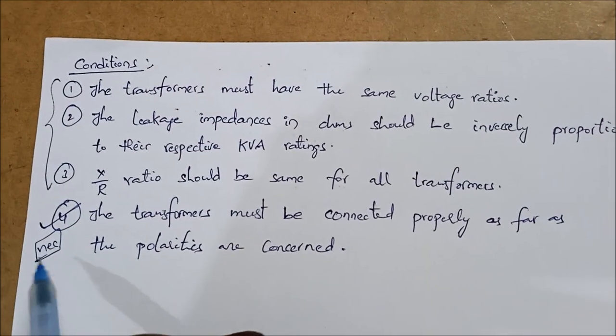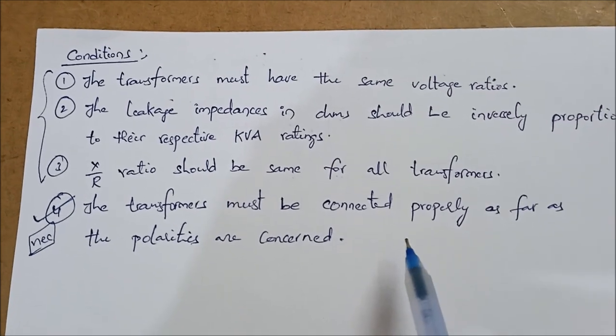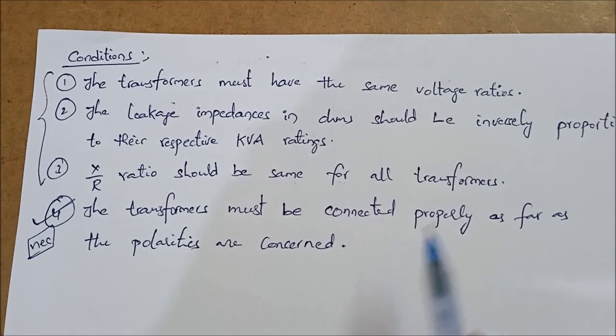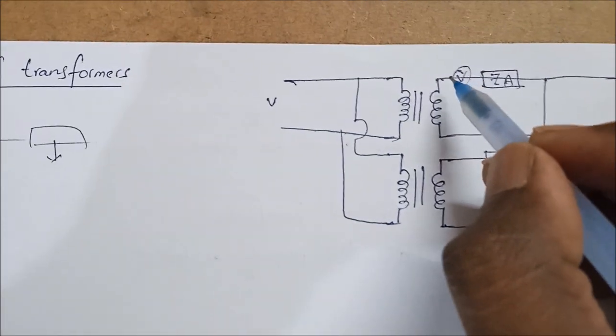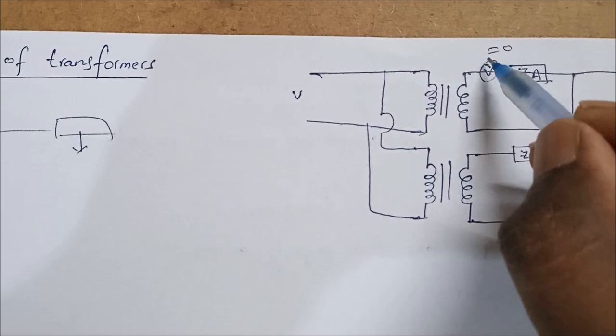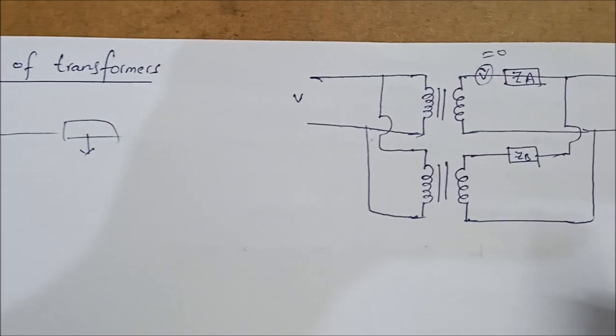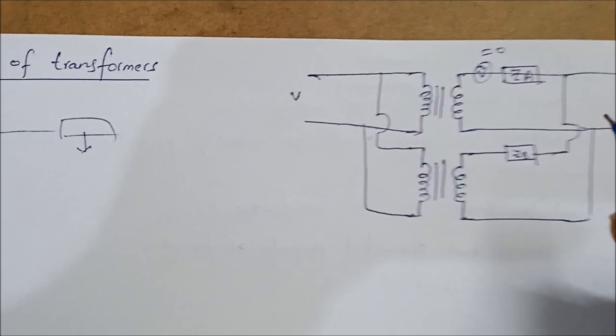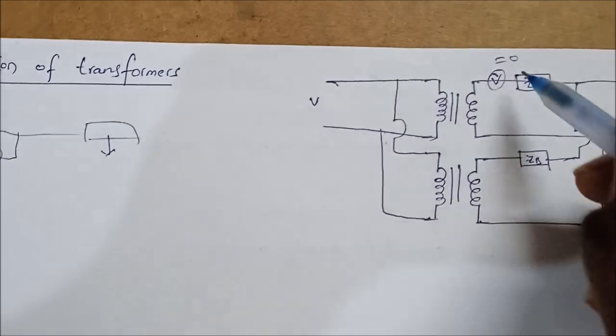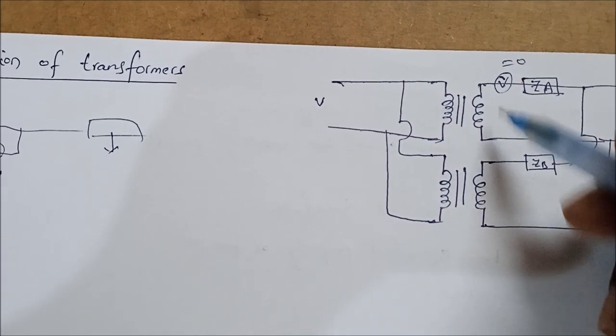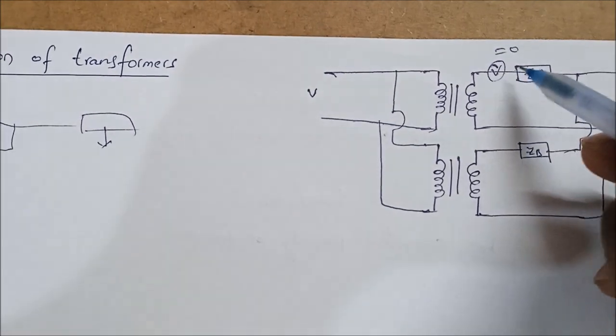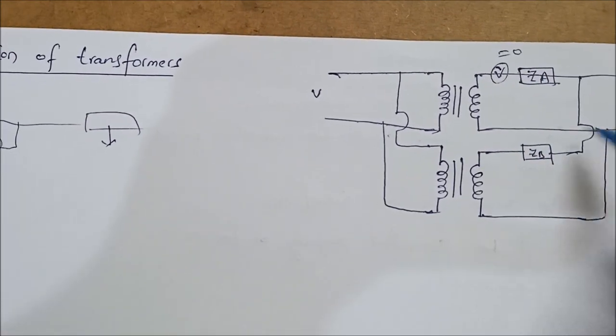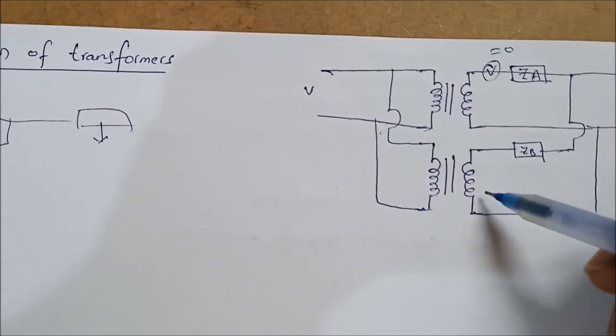The fourth point must be satisfied. If you don't connect the polarities correctly, a large amount of circulating currents will flow. To verify, connect a voltmeter across the secondary terminals before paralleling. If the voltmeter reading is zero, they are connected in proper polarity and there are no circulating currents. If the voltmeter reading equals the sum of the two secondary voltages, there is improper connection and you must reverse the connections of one of the transformers.